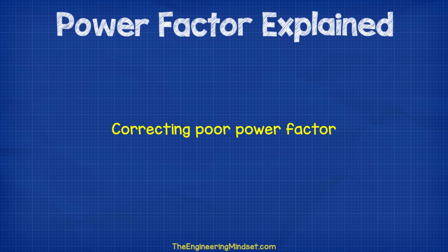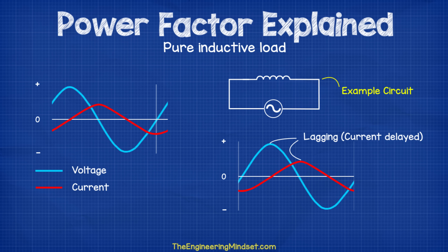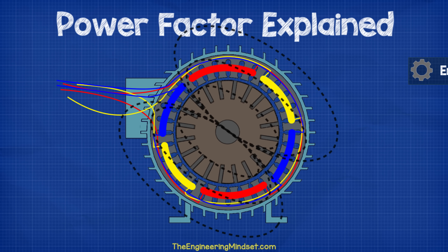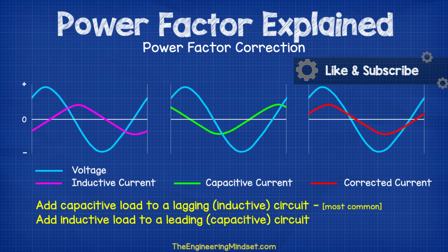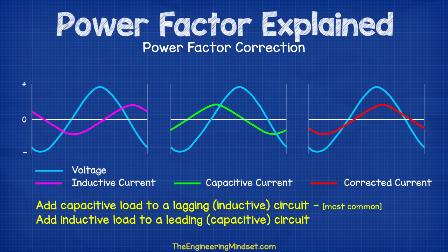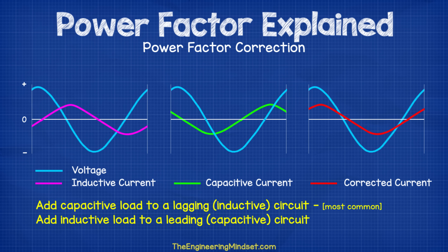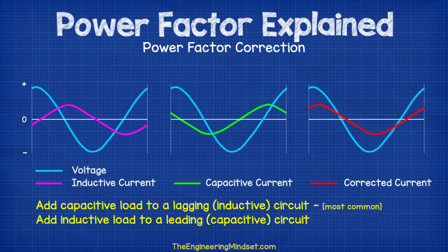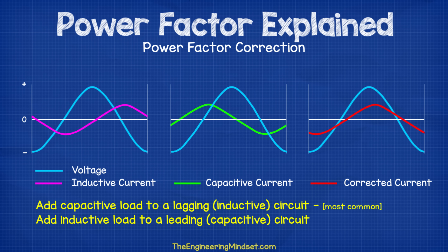Correcting poor power factor — what can we do to correct poor power factor and reactive power charges? In most cases, we come across lagging power factor caused by inductive loads. To correct poor power factor, we can add capacitors or inductors to the circuit, which will realign the current back into phase and bring the power factor closer to one. If we have a lagging power factor caused by high inductive loads, then we add capacitors. If we have a leading power factor caused by high capacitive loads, then we add an inductive load to the circuit. These need to be calculated, and we'll see some example calculations at the end of the video.